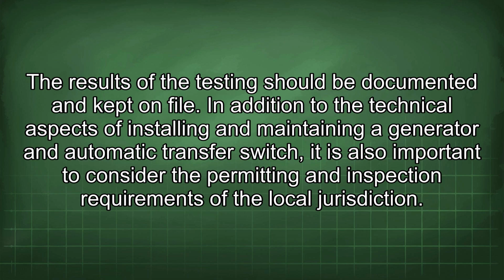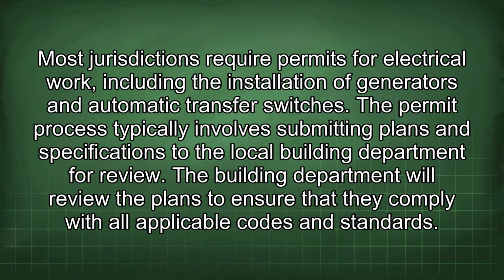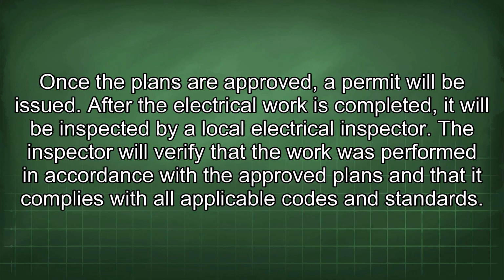In addition to the technical aspects of installing and maintaining a generator and automatic transfer switch, it is also important to consider the permitting and inspection requirements of the local jurisdiction. Most jurisdictions require permits for electrical work, including the installation of generators and automatic transfer switches. The permit process typically involves submitting plans and specifications to the local building department for review. The building department will review the plans to ensure that they comply with all applicable codes and standards. Once the plans are approved, a permit will be issued.